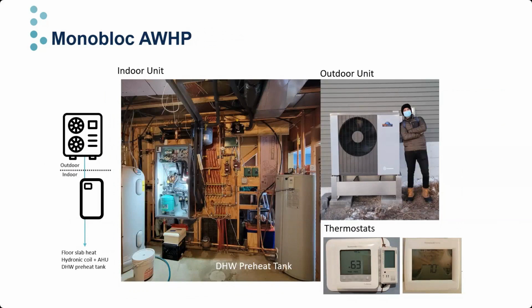And here's the Enertech monoblock system as installed at Site 3 in Faribault. While not a defining feature of a monoblock system, this Enertech unit did have an IDU which included some additional components like a hydronic pump and an expansion tank, as well as system controls. It's a bit hard to see in that picture, but the IDU is the glowing rectangle on the left side of the image. In this image, it's been opened up so we get a good look at its insides, graciously illuminated by that little work lamp.